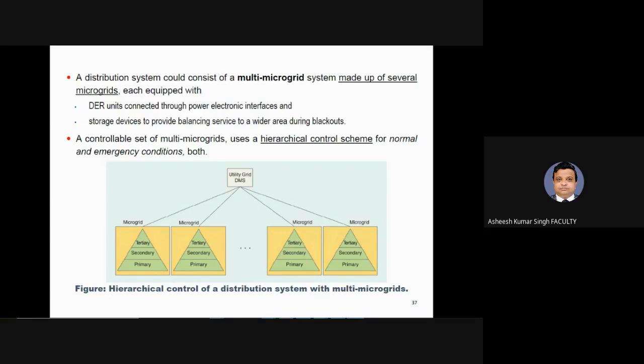This management in multi-microgrid is done by one distribution management system, shown here as the utility grid DMS. This DMS receives control signals from the medium voltage network and individual microgrid master controllers. The DMS performs optimization, then sends proper signals to individual microgrids for load sharing or maintaining rated voltages and frequencies. These are the different steps taking part in the control of multi-microgrids within a distribution system.